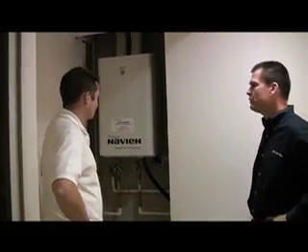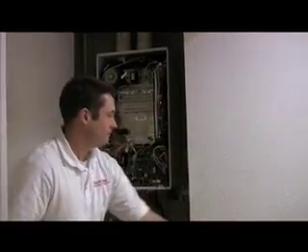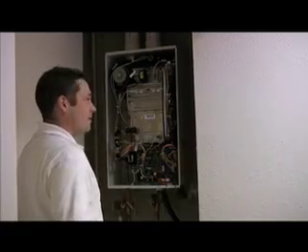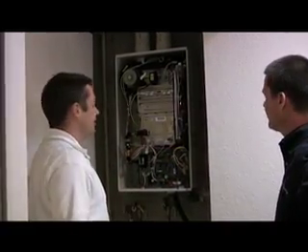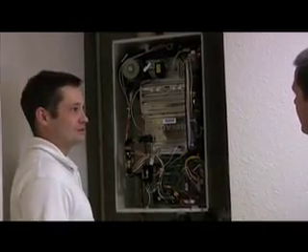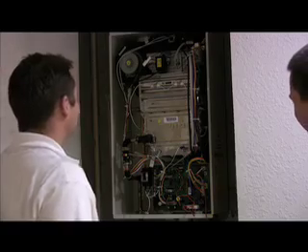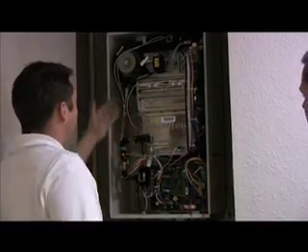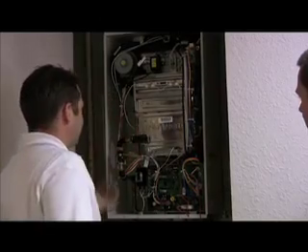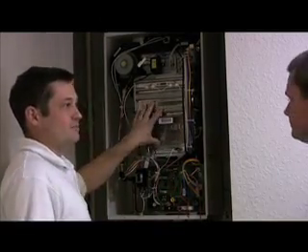Let's crack this thing open and see what it looks like inside. It's a lot of stuff in there — it's not your standard water heater. A little more technology going into a unit like this than your standard tank-type water heater. I don't see any water in there either. No, you don't see any water. Everything's contained within this silver box here — it's a stainless steel heat exchanger, and that's where everything's really happening. The water's passing through this exchanger; that's where all the burners come on and superheat the water as it's passing through the unit.